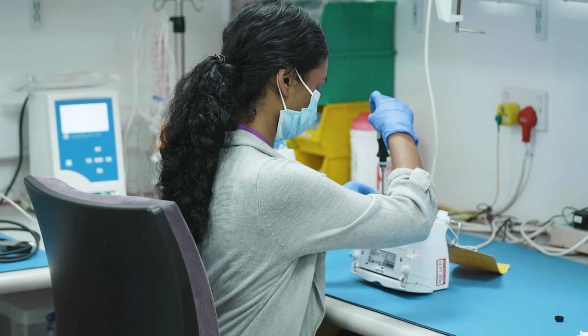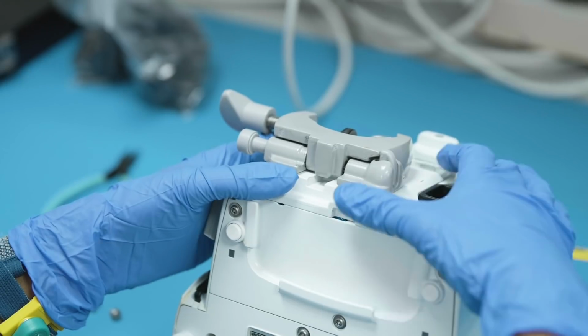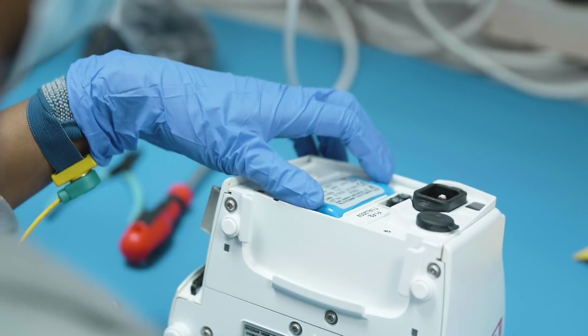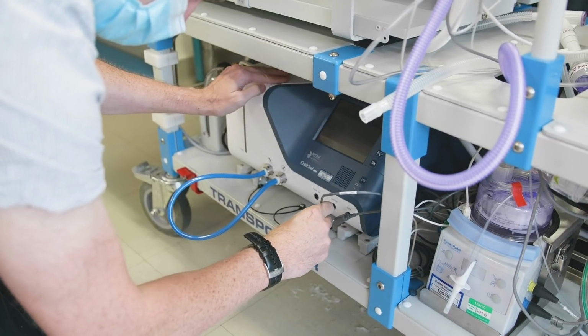Had clinical engineers been considered during all these planning phases? The short answer is no, because there were so many operational problems that had to be sorted out to get the ventilators delivered into the UK, that really putting them into service was the second priority. There was an assumption that clinical engineers would be able to cope as they always had done. And so I thought that it will be fine. They'll manage to make it work when the equipment gets there. However, there were some fairly serious issues when the equipment arrived that meant that wasn't possible, particularly getting spare parts and additional consumables to make it work.